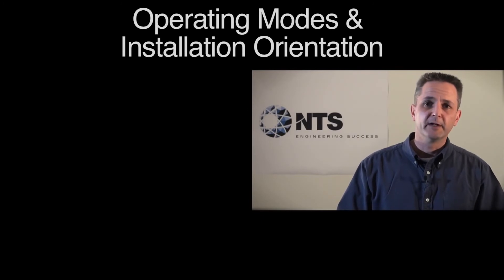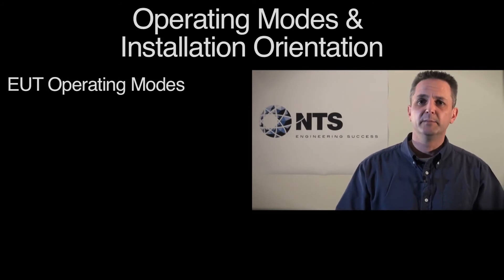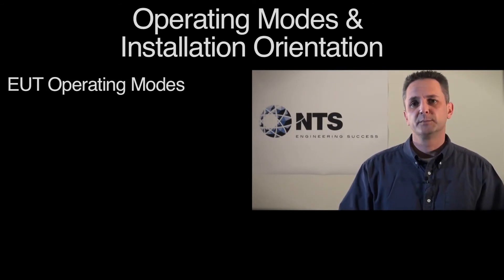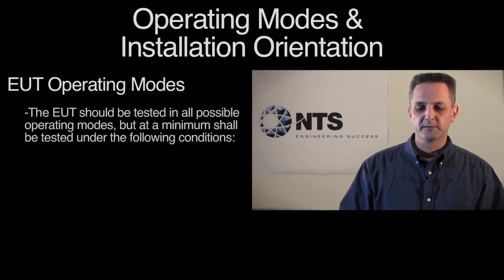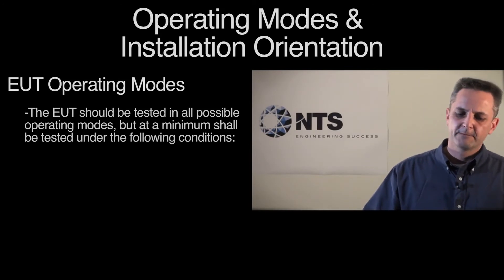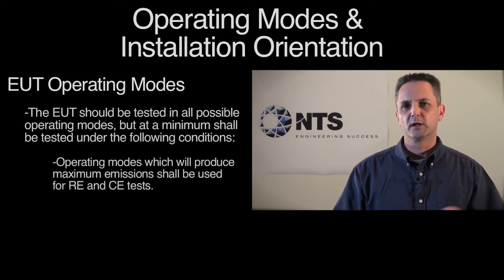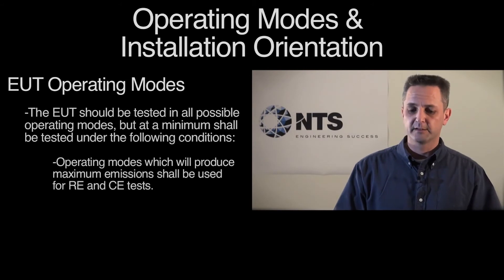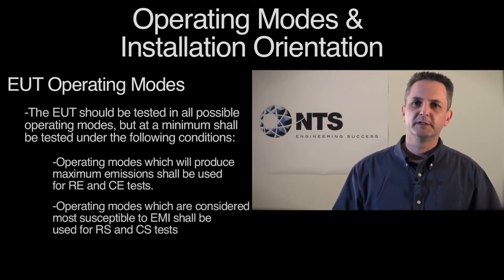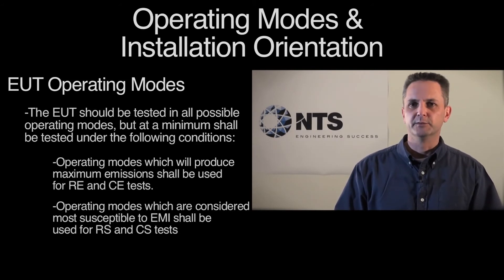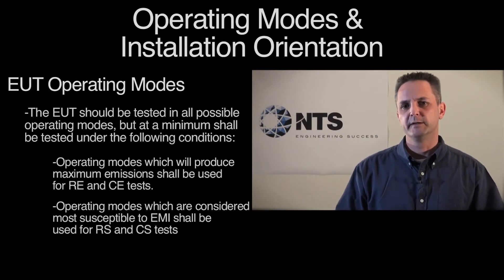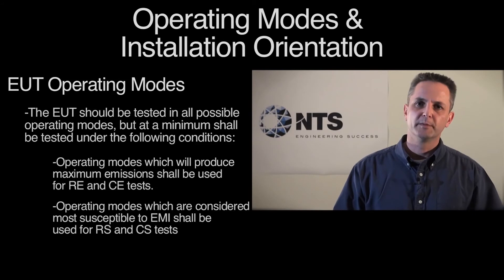The operation of the equipment while it's being tested must be clearly understood. Operating modes can vary depending on the complexity of the equipment, and MIL-Standard 461 specifies that equipment should be tested in all operating modes. At a minimum, operating modes which produce the maximum emissions shall be used for radiated and conducted emissions tests, and operating modes considered most susceptible to EMI shall be used during susceptibility tests. This determines absolute worst case for emissions characteristics and the most vulnerable state of the equipment.